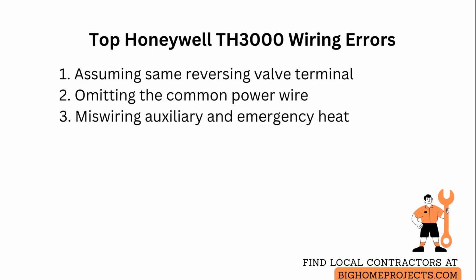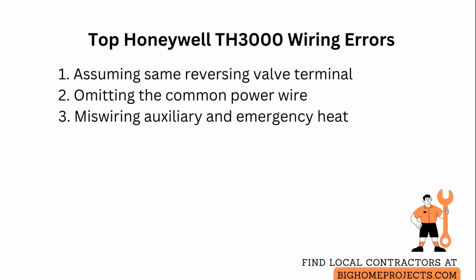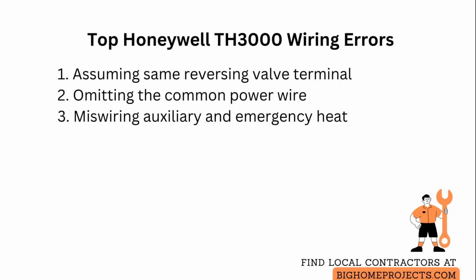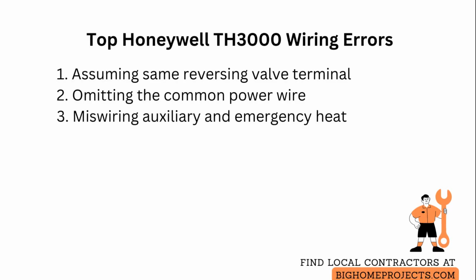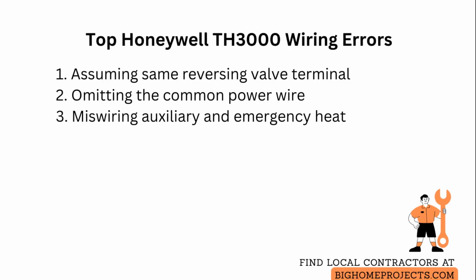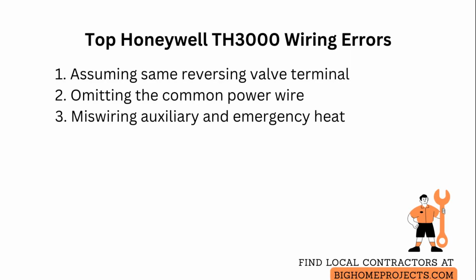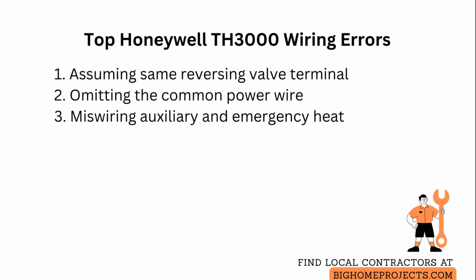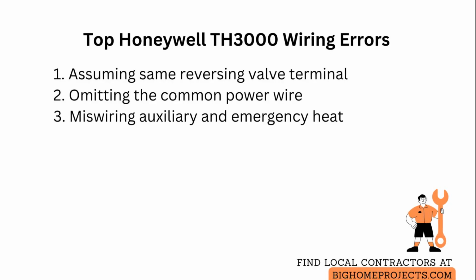Common mistakes include assuming every heat pump uses the same reversing valve terminal, which causes incorrect valve activation and short cycling. Check the outdoor unit label and set the thermostat configuration for O or B accordingly. Another frequent error is omitting the common wire when adding a smart thermostat, which results in intermittent power and rebooting. Run and connect a proper common conductor or use a compatible power extender kit following the manufacturer guidance.